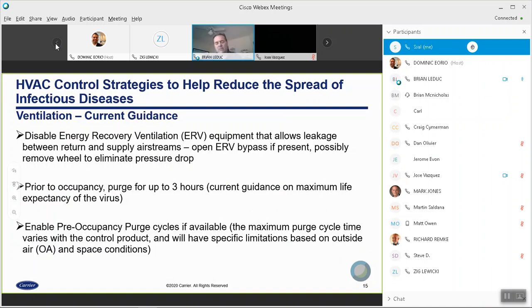So the rooftop units primarily, whether it's ComfortLink or VAV RTU Open or RTU Open, there may be some variance in the maximum amount of pre-occupancy purge that you can enable. But the key is you do want to enable it wherever possible, with the understanding that the system is designed with limitations to prevent pre-occupancy purge in cases where the outside air conditions are not suitable. So there may be limits to what you can achieve without modifications to the logic or the sequences.